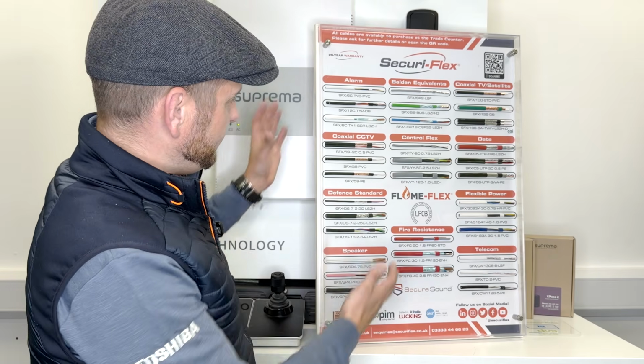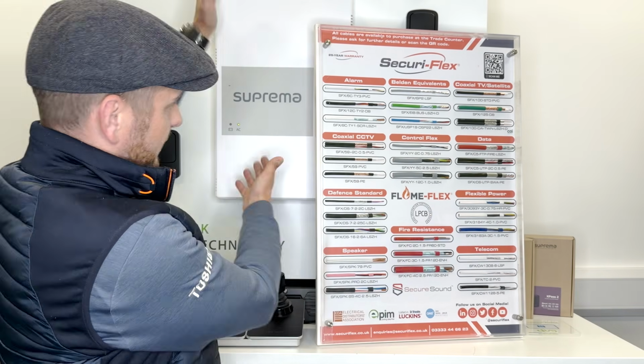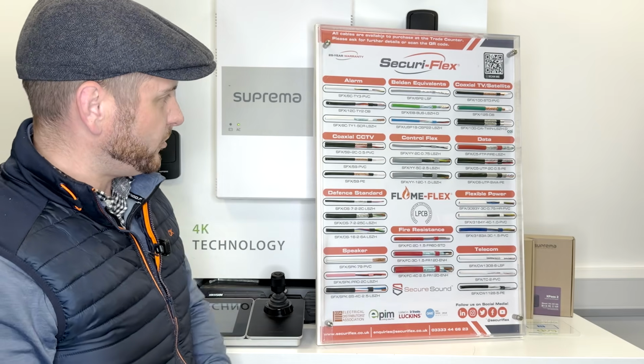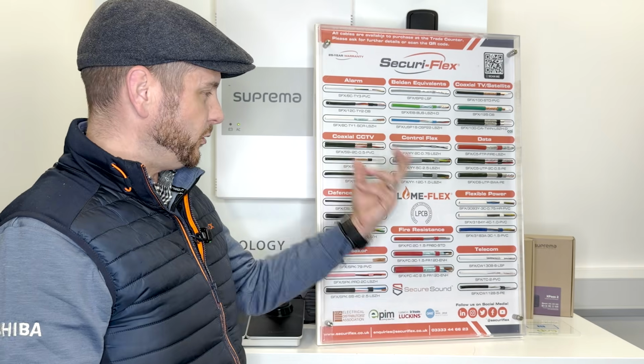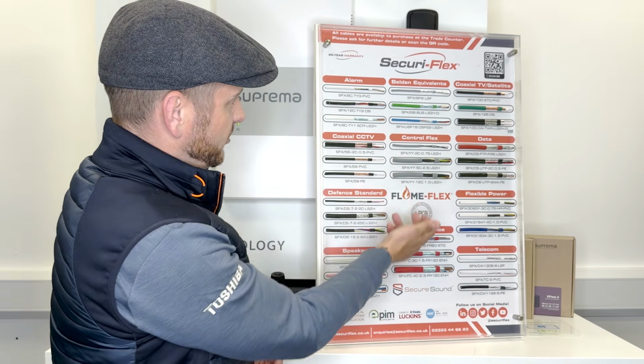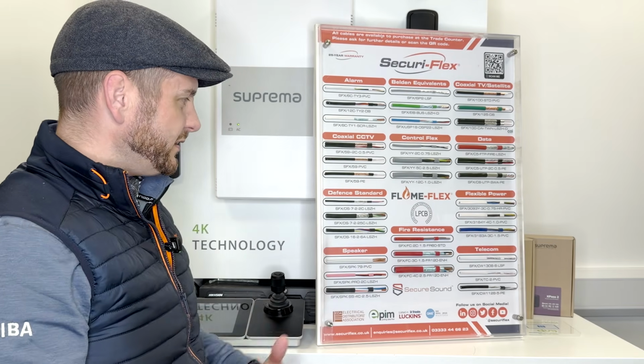And again, out of this lovely selection of cables, we can have the power cables, and that would be to control the ACU that we talked about. Or you can have the door control cable, so your Maglock cable typically will be wired in a 2-core 0.75 flex from the power supply location to the Maglock location, or the lock control mechanism that is used on your choice. And that could be from your control flex, or it could be from your flexible power cable. It depends on the power draw and the voltage required at that door controller itself.